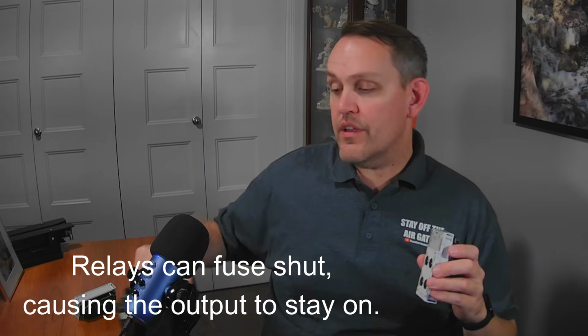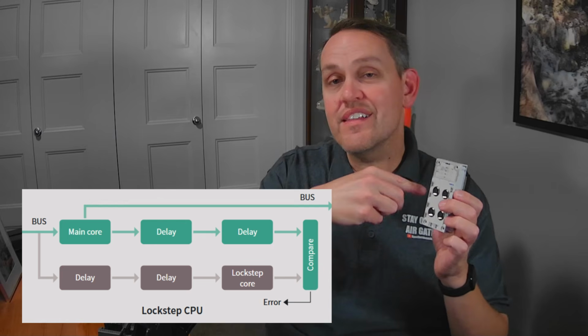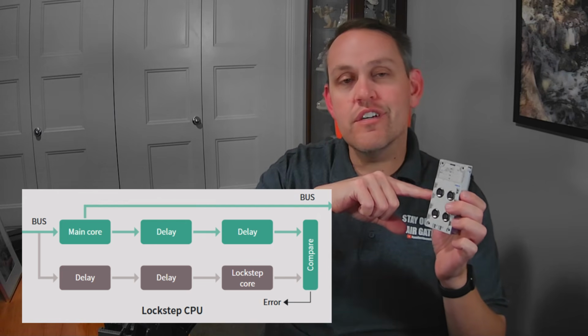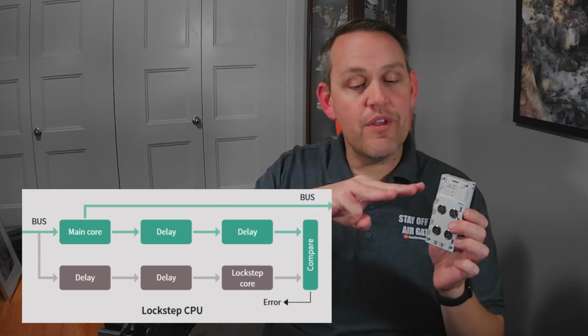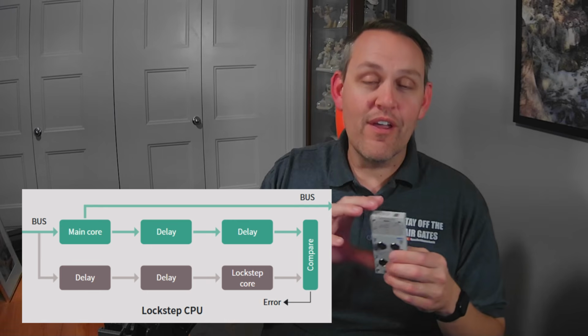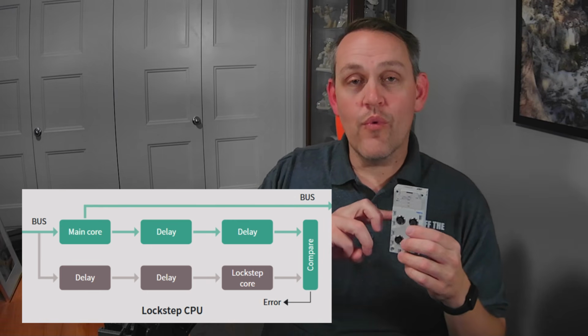The I/O cards have the same exact thing inside of them. In fact, they also have little processors on the I/O card itself. And now we have safety rated I/O, which means on the old stuff you would have one little relay that closed and turned that output on. And now, to turn that output on, you have to have all 3 safety processors agree to turn that output on, and then it uses 2 gates, 1, 2, and once 1, 2 gates agree on the inside of that output, it turns on the 3rd gate and actually allows the signal to go out. And all 3 of those gates internally are monitored. So if my 1, 2 close but the 3rd one doesn't, or 1 closes and 2 never does, then the I/O card itself knows that there is a problem.